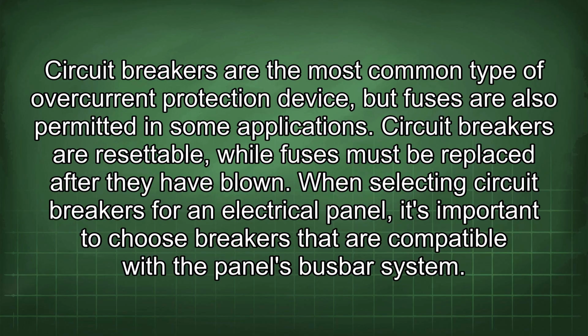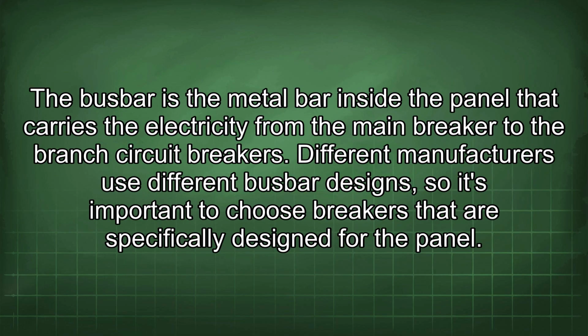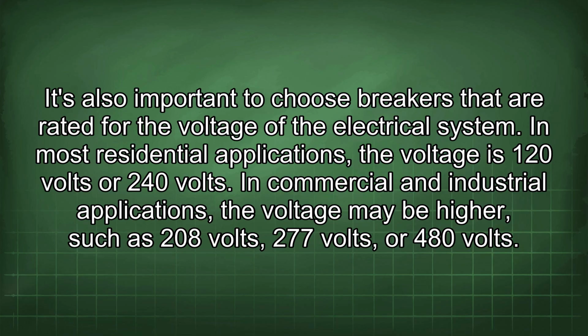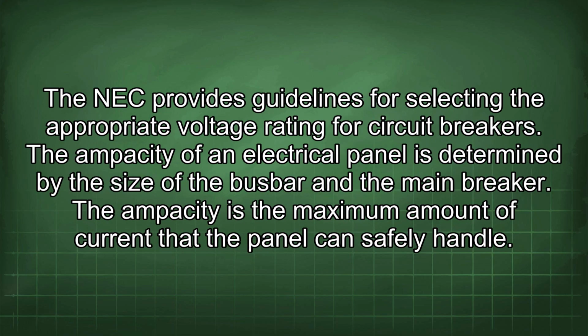When selecting circuit breakers for an electrical panel, it's important to choose breakers that are compatible with the panel's busbar system. The busbar is the metal bar inside the panel that carries the electricity from the main breaker to the branch circuit breakers. Different manufacturers use different busbar designs, so it's important to choose breakers that are specifically designed for the panel. It's also important to choose breakers that are rated for the voltage of the electrical system. In most residential applications, the voltage is 120 volts or 240 volts. In commercial and industrial applications, the voltage may be higher, such as 208 volts, 277 volts, or 480 volts. The NEC provides guidelines for selecting the appropriate voltage rating for circuit breakers.